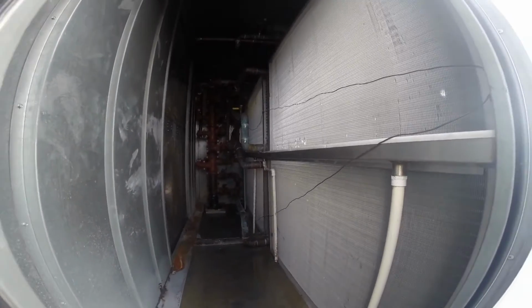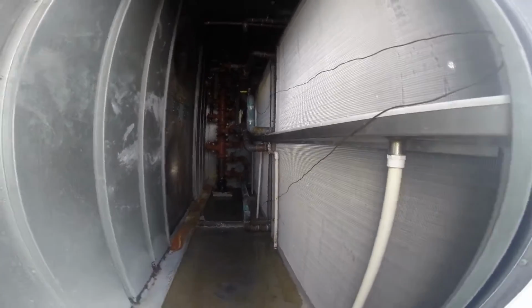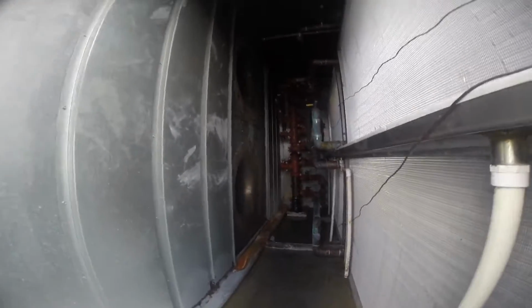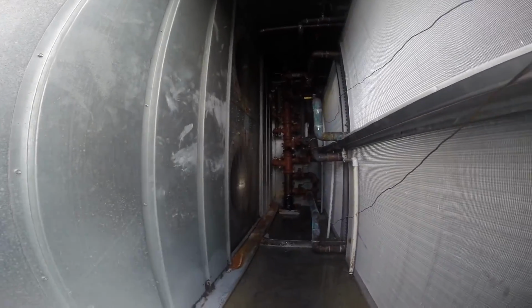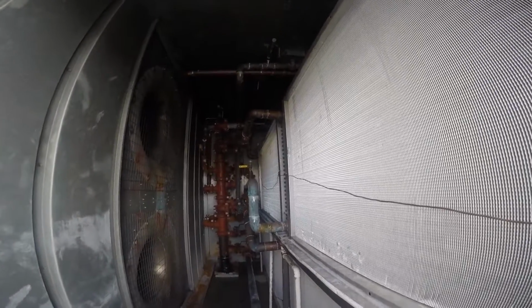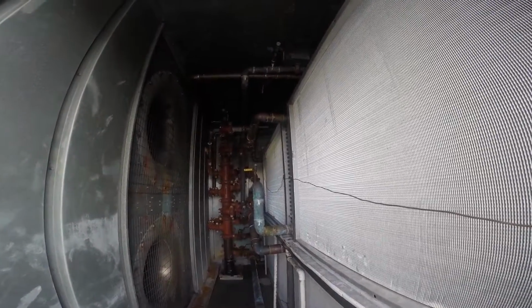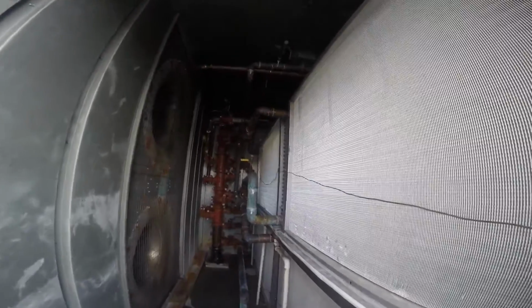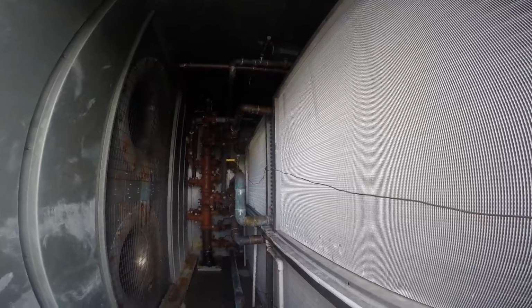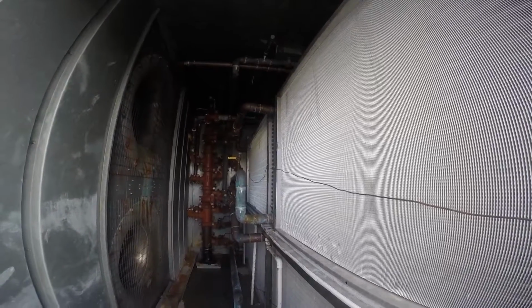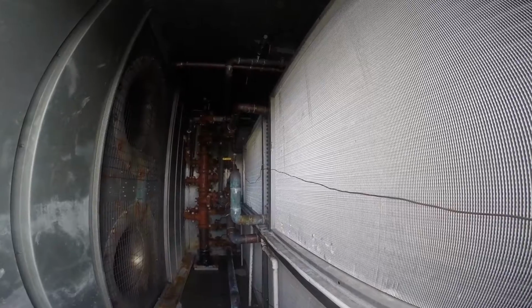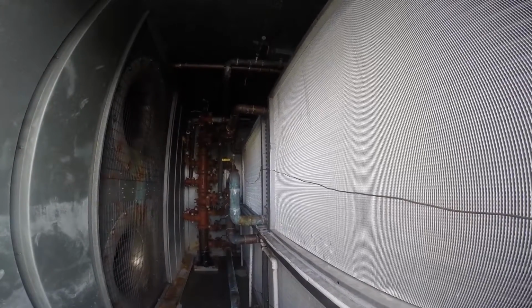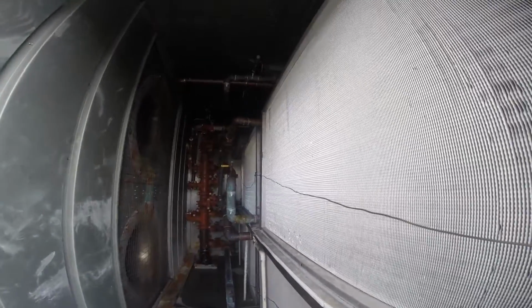This would be the outlet side of the chilled water coils, or the inlet, also the inlet to the blowers right there. If you look up there in the top corner, you'll see where somebody's jumpered out the freezestat, which if we're going to 100% outside air, that freezestat will have to be moved over up to the supply air in order to make sure we don't dump cold air down into the space.